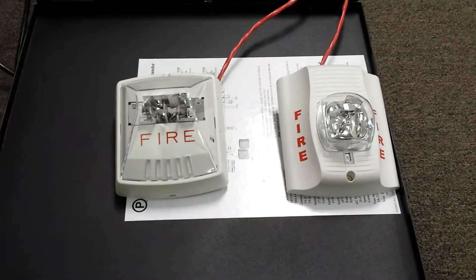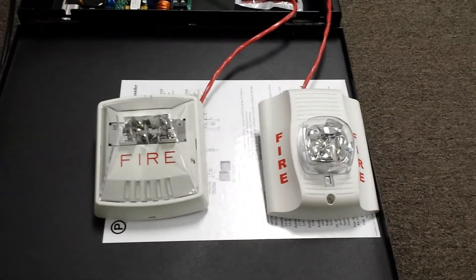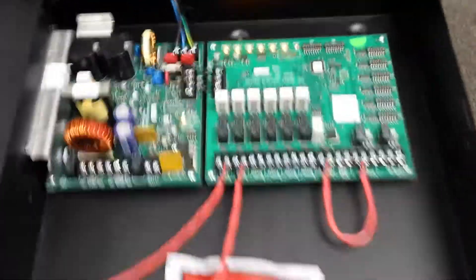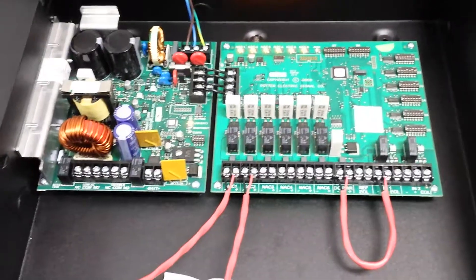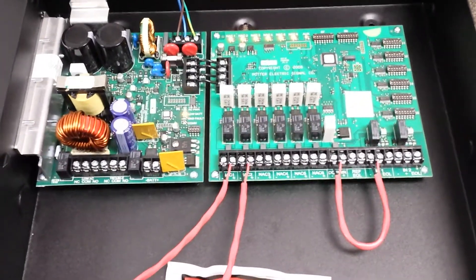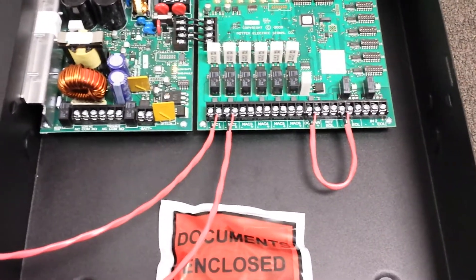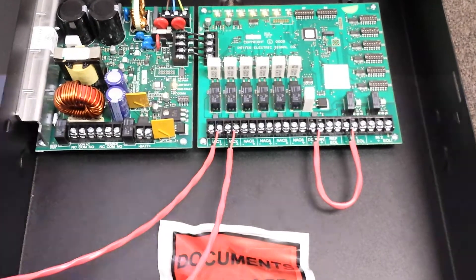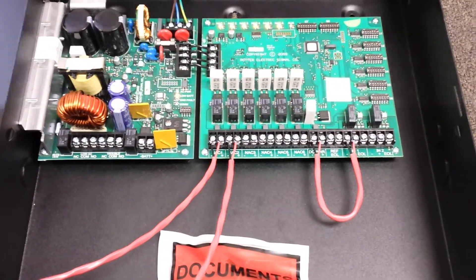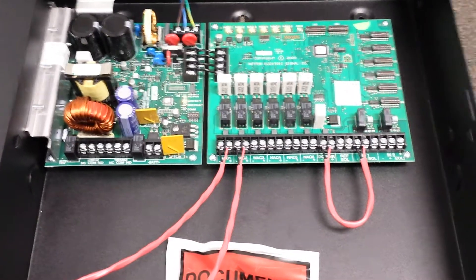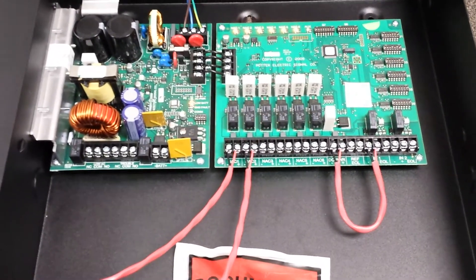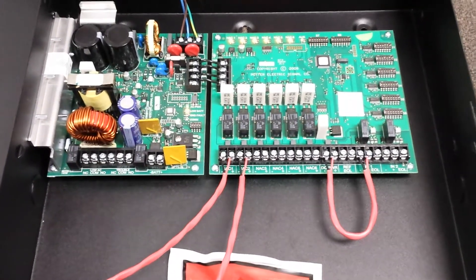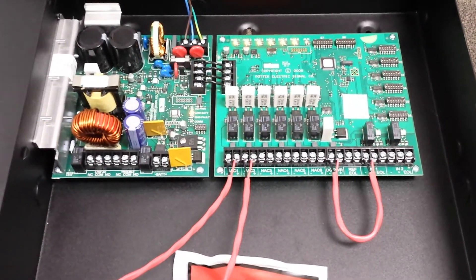Another cool feature it does is the ability to have a memory for the troubles. So there is a dip switch you can set on this. I didn't set it for this particular demo, but if you're trying to track a trouble situation on this panel, such as a ground fault or a particular NAC circuit that's going in and out of trouble intermittently, this thing will keep track of it, so when you show up to the service call and the panel is normal, you can go through the memory and see which of the circuits was giving you that trouble condition, so it makes it a little bit easier to track it down if the trouble is not present at the time of your arrival to that call.